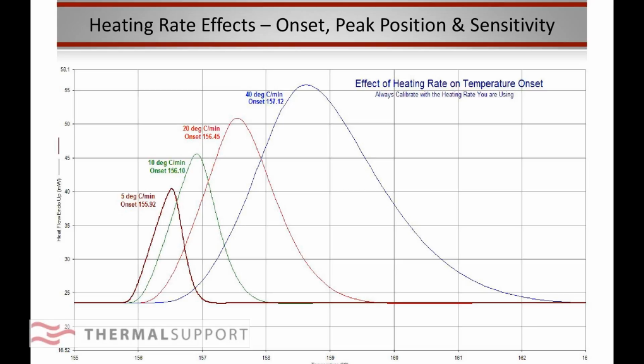The next thing, remember, you've got heating rate effects. If you're going to be running samples, you may be in a lab that has multiple samples. You may run some at 10 degrees a minute, some at 20, some at 40. So remember, if you're going to run at different heating rates, you're going to need different calibrations to go with the samples that you run at 20, that you run at 30 or 40.